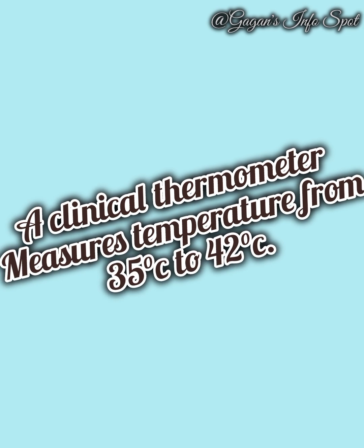One of the most important things about the clinical thermometer is the temperature it measures. So it measures the temperature between 35 degrees Celsius and 42 degrees Celsius. Above and below the given temperature it cannot measure.